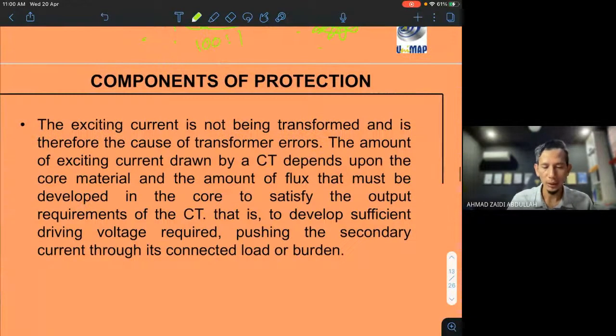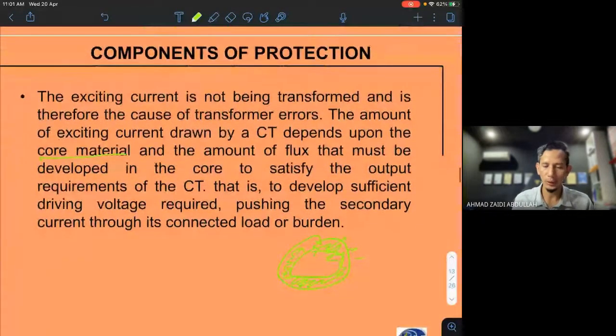Alright, the exciting current is not being transformed, and therefore it causes transformer error. The amount of exciting current drawn by the CT depends upon the core material, the type of core that you are choosing, and the amount of flux that must be developed in the core to satisfy the output requirement of the CT. The flux will develop here. There is a coil here, this is the input, and then this is the output.